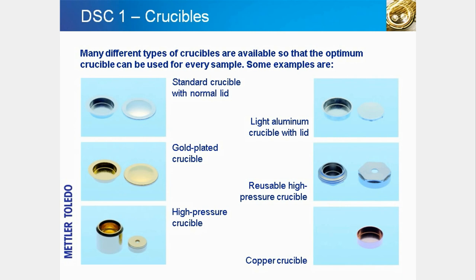Depending on the sample and measurement requirements, other crucibles may also be needed. For example, gold crucibles are available for samples that react with aluminum. A common application is to measure a sample in a closed atmosphere and at a higher pressure than ambient — these measurements can be performed using a high-pressure crucible. In fact, there are more than 25 different types of crucible to match the requirements set by the sample and application.